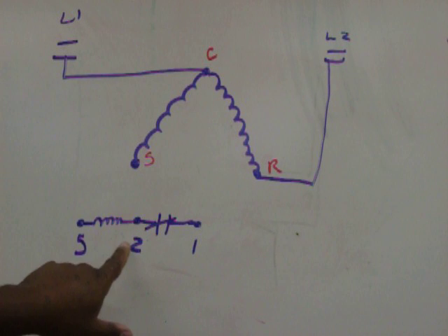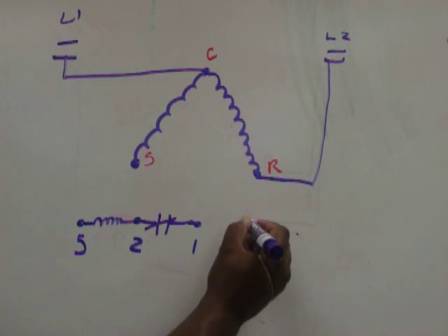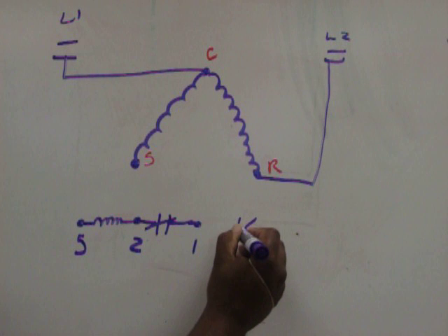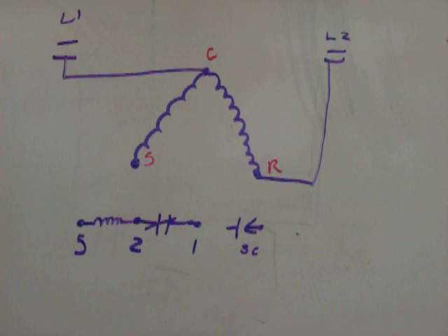So you'd have to have your start winding. And start winding is going to assist the run winding in getting the motor started. Once you get started, the potential relay is going to drop the start winding and the start capacitor out. So let's put a start capacitor right there. Very simple to wire this up.